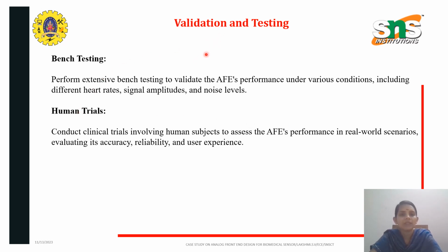The next is validation and testing, which is a very important phase here. We have to perform extensive bench testing to validate the performance under various conditions. That is, the front end circuit's performance has to be monitored under different heart rates, signal amplitudes, and noise levels. And the next is the human trials. We have to conduct clinical trials involving human subjects to assess the analog front end's performance in real world scenarios, such that we can evaluate its accuracy, reliability, and the user experience.